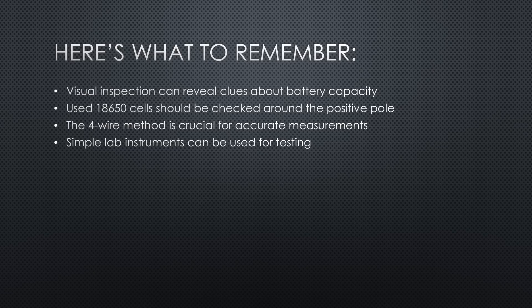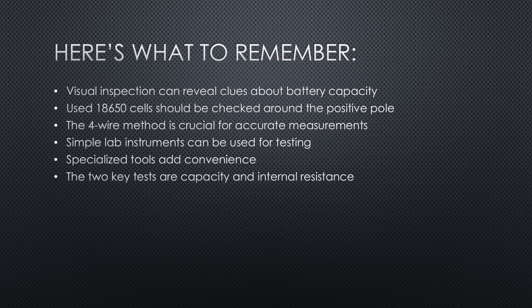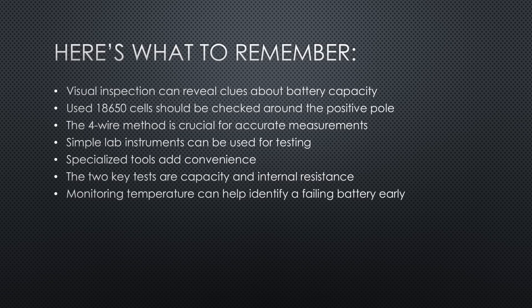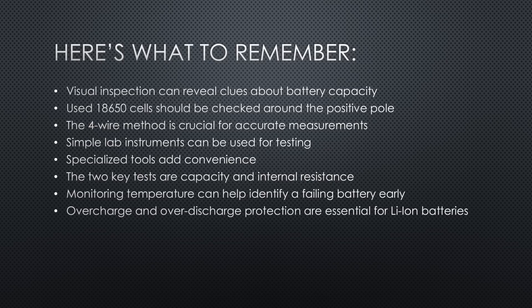Simple lab instruments can be used for testing, while specialized tools add automatic charging and discharging for convenience. The two key tests are capacity and internal resistance. Monitoring temperature can help identifying a failing battery early. This method is often used in battery packs.